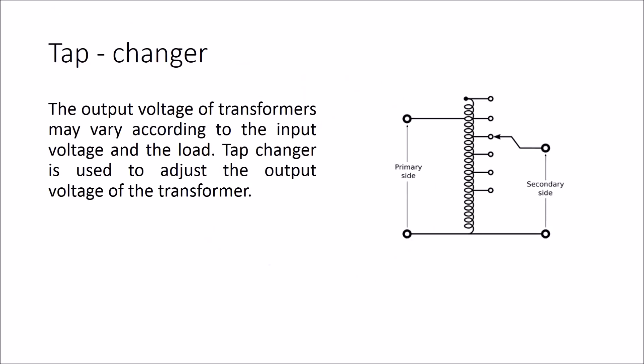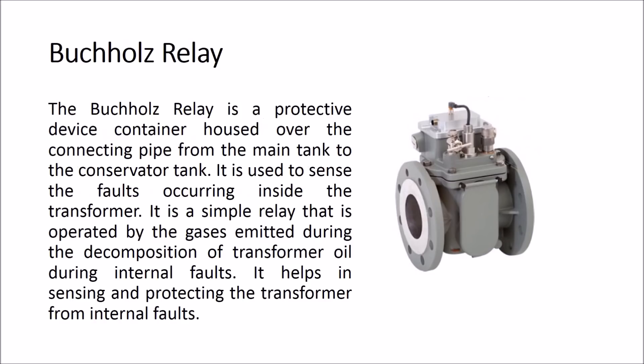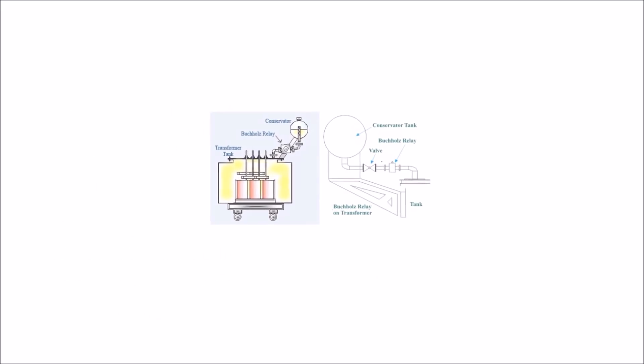The output voltage of a transformer may vary according to the input voltage and the load. The tap changer is used to adjust the output voltage of the transformer. The Buchholz relay is a protective device housed over the connecting pipe from the main tank to the conservator tank. It is used to sense faults occurring inside the transformer. It is a simple relay operated by gases emitted during the decomposition of transformer oil during internal faults, helping in sensing and protecting the transformer from internal faults.